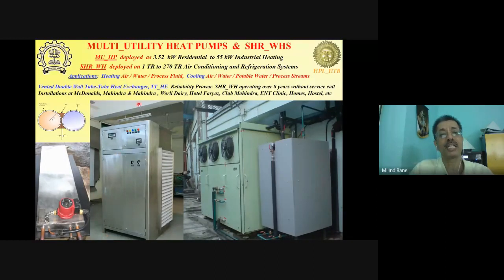So getting started, first I would like to take you through the multi-utility heat pumps and superheat recovery water heater. So as I said, a multi-utility heat pump generates more than one utility using a single refrigeration system or air conditioning system. The configuration of the system, the cycle is very similar to what we have in a refrigerator or an air conditioner or a heat pump. The only thing is the heat exchangers are judiciously integrated in such a way that we can generate multiple utilities, like this particular unit, which was deployed in Mahindra and Mahindra in an automotive factory. The primary purpose of this was to heat up cleaning solution in washing machines from 50 to 55 degrees centigrade. Now, while the solution was being heated with the condenser heat, the heat was being picked up on the evaporator side from the room air or the shop floor air.